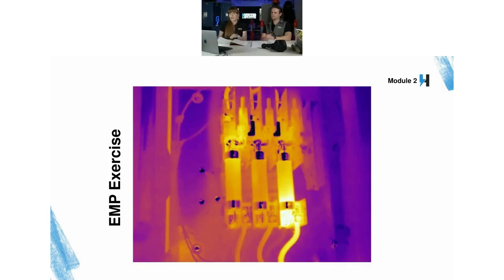Absolutely. And Lisa, you asked how often do you have to have the infrared scan done? It depends on the condition. It's every year. If it's a condition 3, it's every year. Well, that's one of the electrical tests, but for any connection point, there is a requirement for infrared scans to be performed every year, I believe. And then if it's in a condition 3, it's actually every 6 months. I will take a moment to find that exact reference, but I've definitely read that before. You're right. My apologies. In the same table we've been referencing, it's right there at the very top.